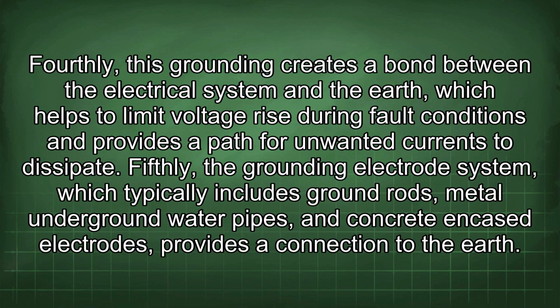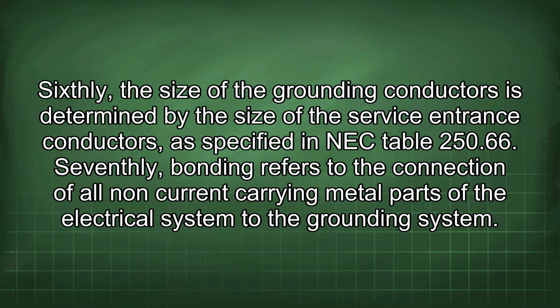Fourthly, this grounding creates a bond between the electrical system and the earth, which helps to limit voltage rise during fault conditions and provides a path for unwanted currents to dissipate. Fifthly, the grounding electrode system, which typically includes ground rods, metal underground water pipes, and concrete encased electrodes, provides a connection to the earth. Sixthly, the size of the grounding conductors is determined by the size of the service entrance conductors, as specified in NEC Table 250.66.